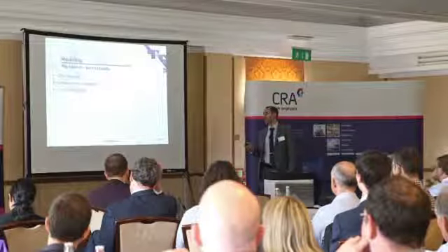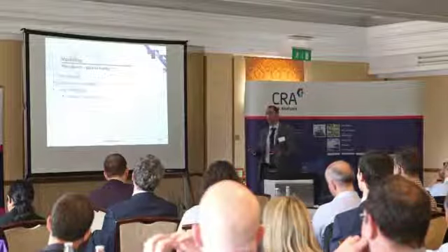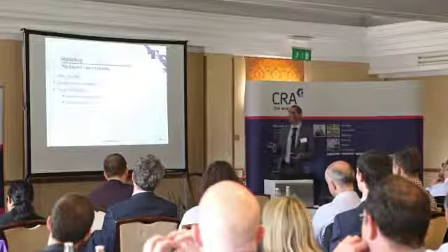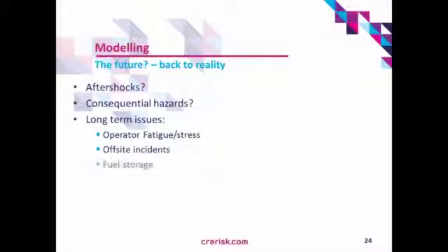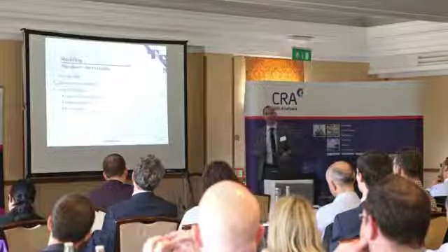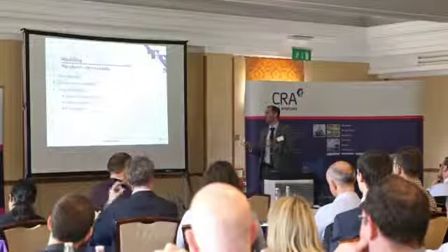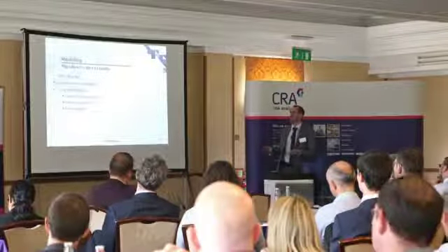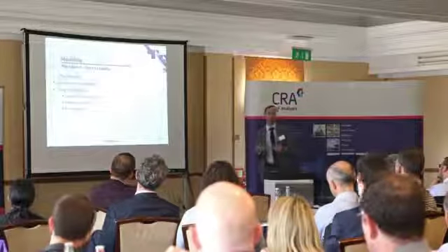But there are other, longer-term issues, such as operator fatigue and stress. You could do it with HEPs, but again, it's quite difficult. Off-site incidents: what happens if you have an installation off-site that is struggling as a result of the seismic event and that's going to come on-site and give you trouble? Fuel storage: I've not really dwelled on it, but obviously the fuel pond is essentially like a mini reactor, so that's just as important. And especially when we talk about long-term issues, it's something generic for PSA. We do struggle when we go beyond 24 hours. Uncertainty is a big part of that, but also things such as data.